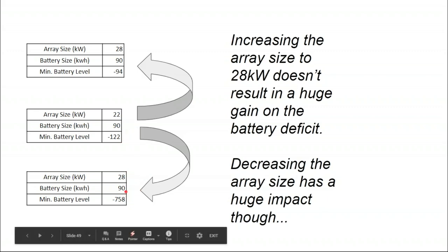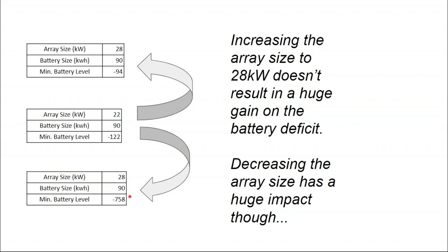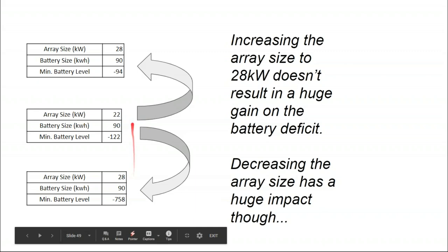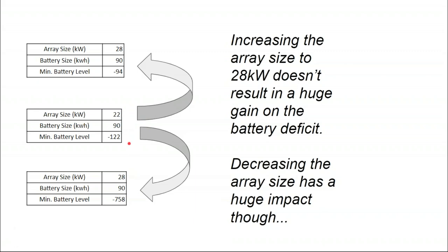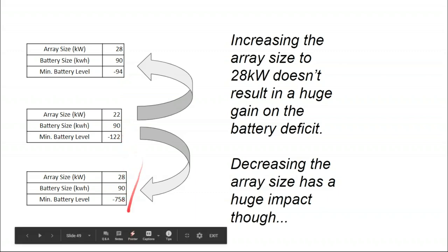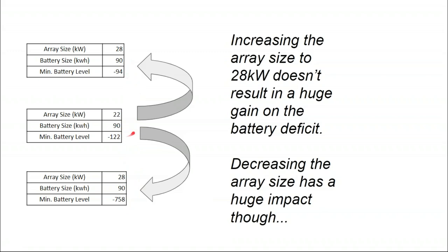So the point of this slide was to say, if you go from a 14 kilowatt array, your battery bank would need to be 760 kilowatt hours. Then you increase that from 2 pallets to 3 pallets and go with 22, you save 630 kilowatt hours out of your battery bank by doing a larger solar array. Then the next step up, from 3 pallets to 4 pallets of solar, instead of saving 600 and something kilowatt hours, you only save 30 kilowatt hours. So you're approaching the upper limit where increasing the array size further makes less sense. I like testing out these different extremes.